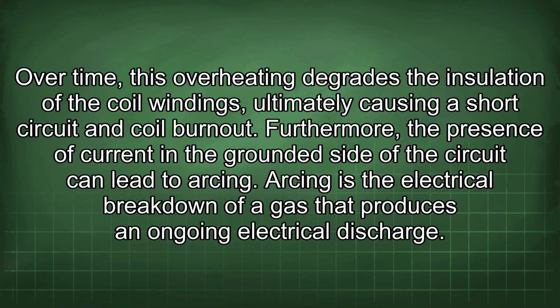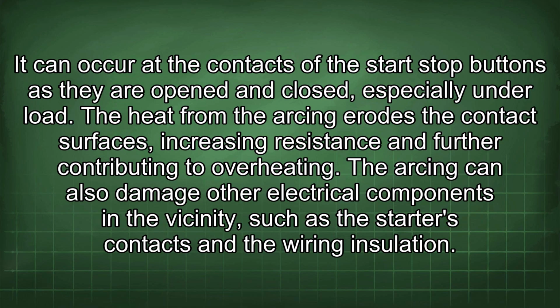Furthermore, the presence of current in the grounded side of the circuit can lead to arcing. Arcing is the electrical breakdown of a gas that produces an ongoing electrical discharge. It can occur at the contacts of the start-stop buttons as they are opened and closed, especially under load. The heat from the arcing erodes the contact surfaces, increasing resistance and further contributing to overheating. The arcing can also damage other electrical components in the vicinity, such as the starter's contacts and the wiring insulation.